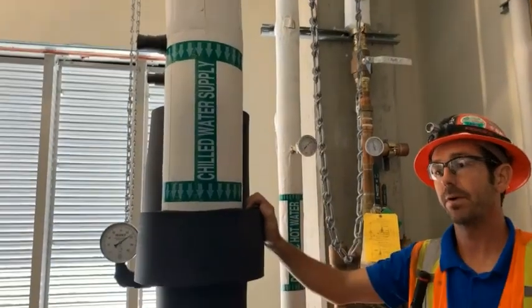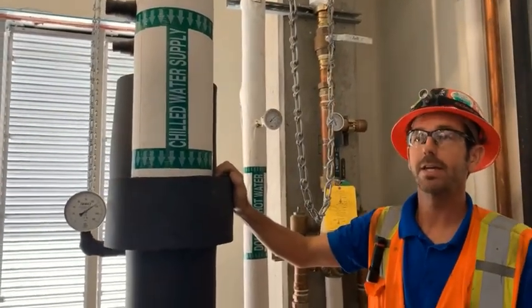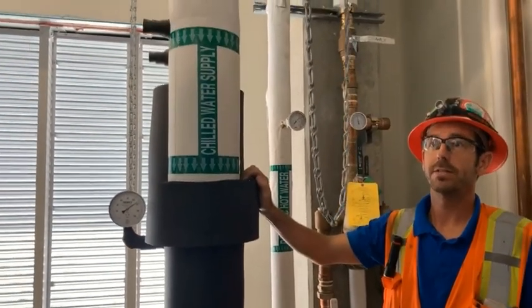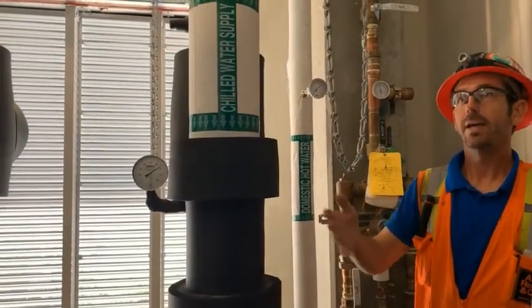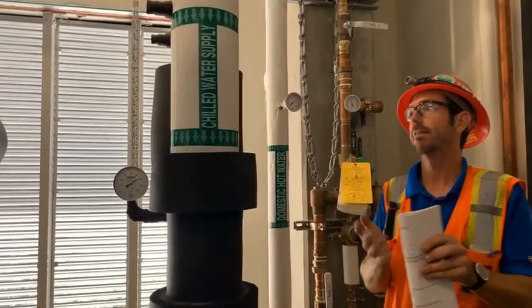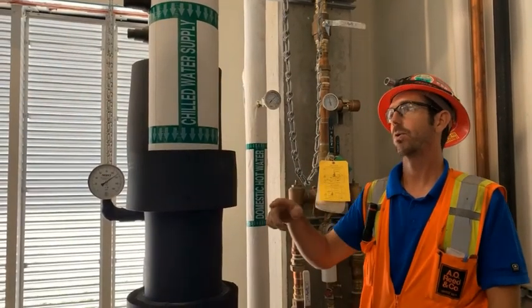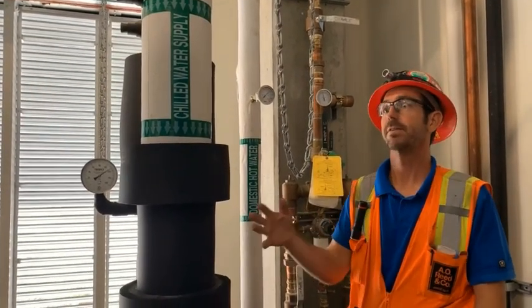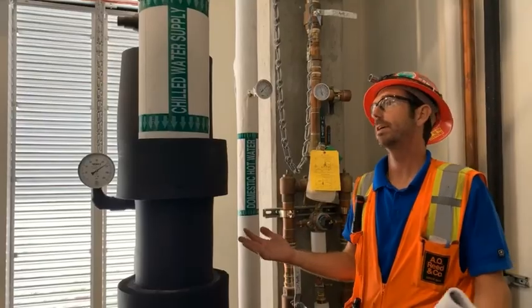This is a little different. If you have a leak on the hot and someone tries to use water, they can. If they leave a single faucet open, the cold will backfeed, and vice versa. So if you do have a leak, you've got to shut everything down.